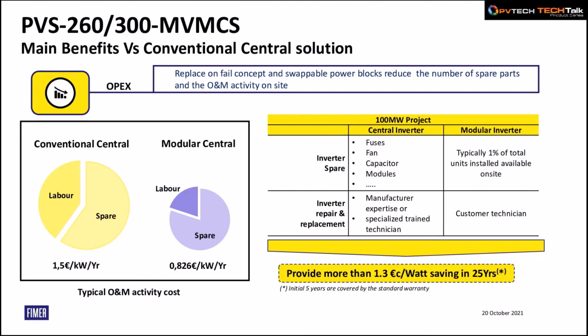Comparing the modular inverter with the central inverter in terms of spares, for a central inverter you have to spare a bunch of different components: fuses, fans, capacitors, modules. The reason is that all failures are converted into repair on site. So for every single failure, you have to go on site, open up the box, and replace the single functional building blocks which have been suffering the failures. While for modular inverters, it is all about swapping a power module.